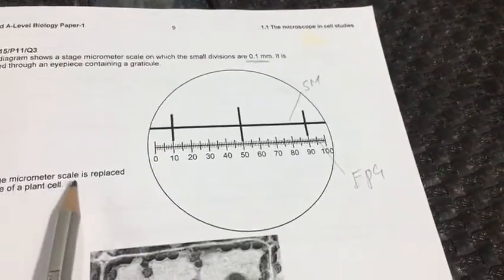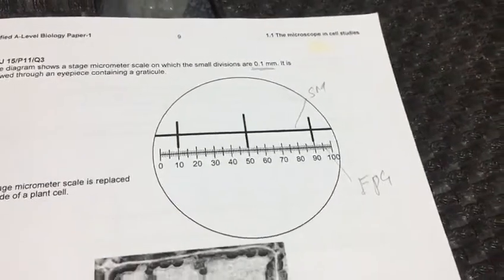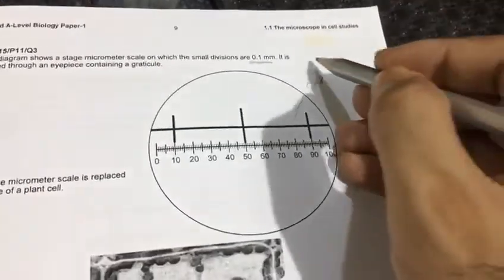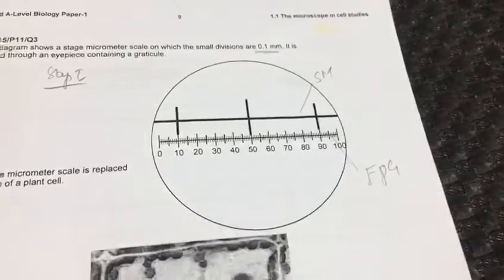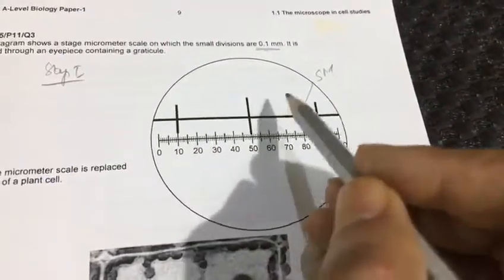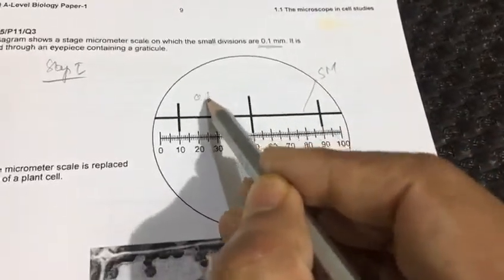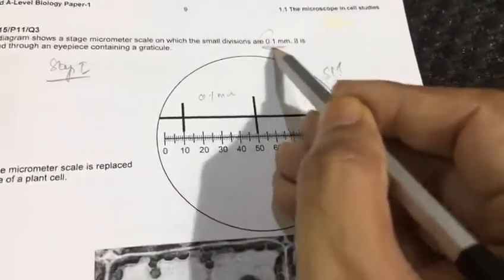The stage micrometer scale is replaced by step 1. What do we do first? We calibrate the one division of EPG. We already know the one division of stage micrometer is 0.1 mm which is printed in this question.